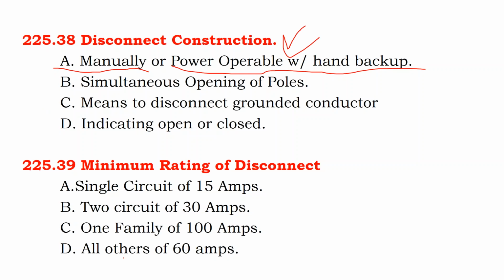Some of these others, let's see, there are some minimum disconnect ratings. This is the one that I think is important, for a single family home. We have this requirement for a minimum service of 100 amps. So if you want to get into, say, tiny home construction, and you're wondering what size service panel you need: obviously, 200 amps for a huge home, but what about for a tiny home? You need to be putting in a 100 amp service panel for a dwelling unit.